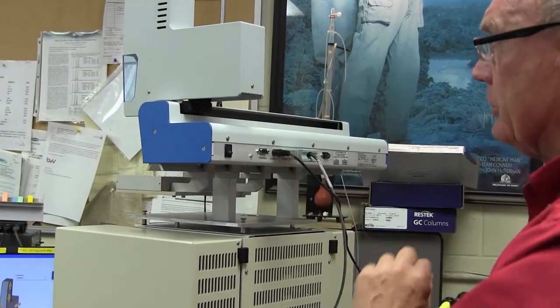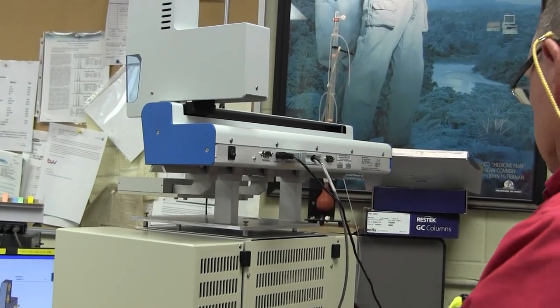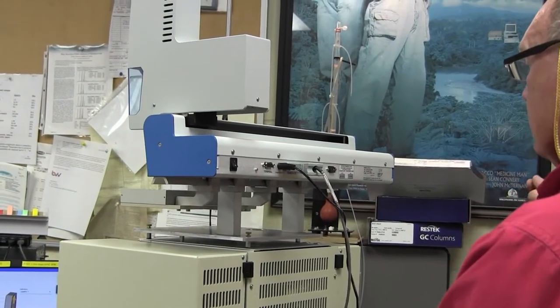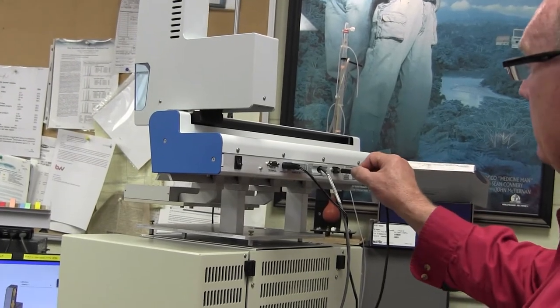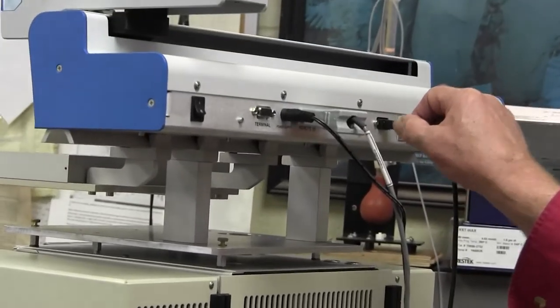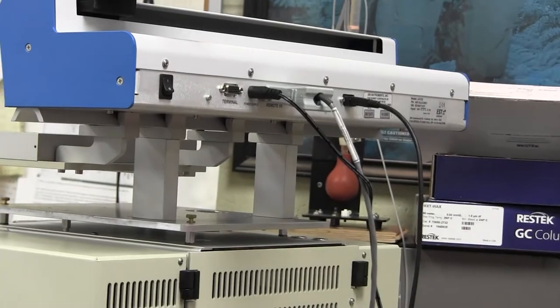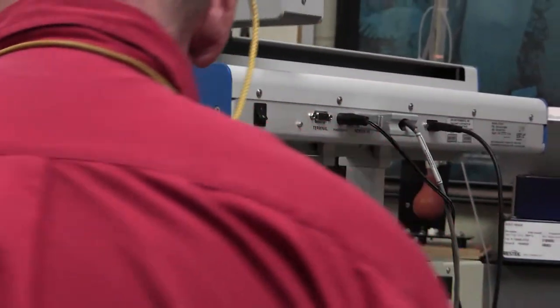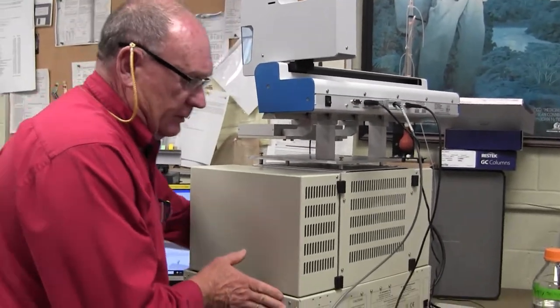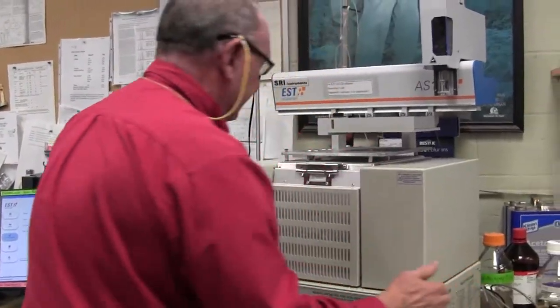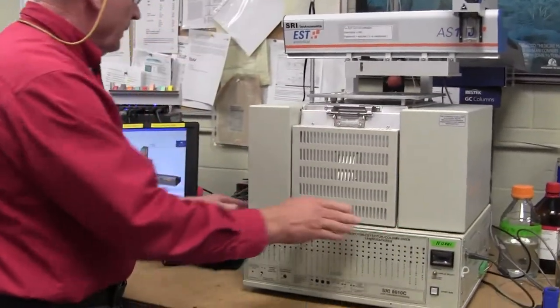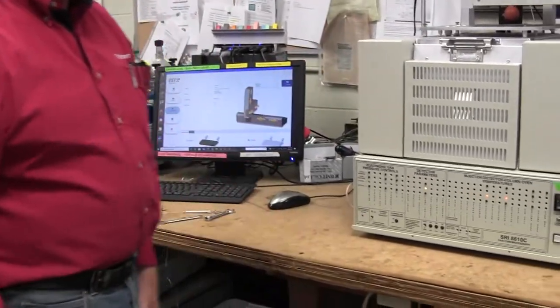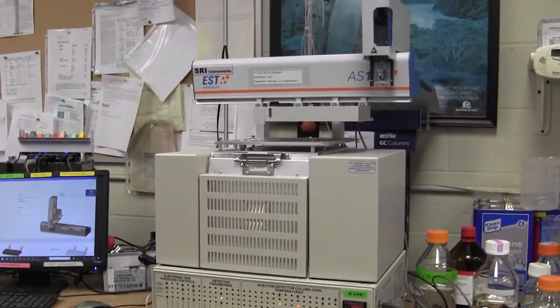Basically the auto sampler is going to its home position which is where it goes to start every sequence. And then finally I'm going to plug the USB cable back in and I heard a little ding dong on the computer so that means it recognized it. Okay so far so good. So turn this GC around and then I'll turn on the power to the GC. So now the GC is under power and so is the auto sampler.